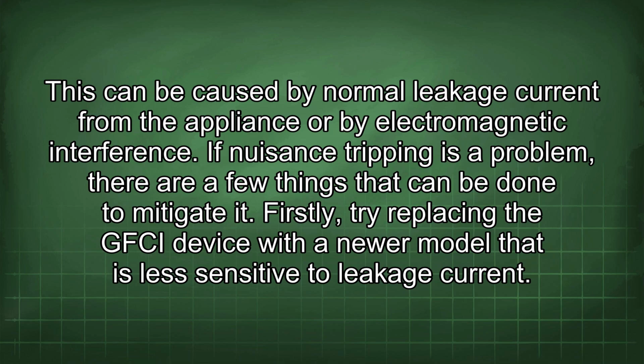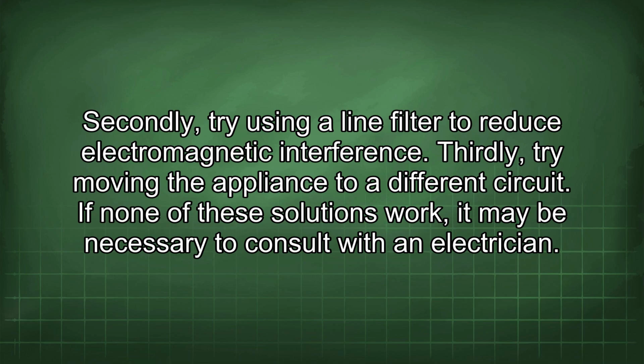If nuisance tripping is a problem, there are a few things that can be done to mitigate it. Firstly, try replacing the GFCI device with a newer model that is less sensitive to leakage current. Secondly, try using a line filter to reduce electromagnetic interference. Thirdly, try moving the appliance to a different circuit. If none of these solutions work, it may be necessary to consult with an electrician.